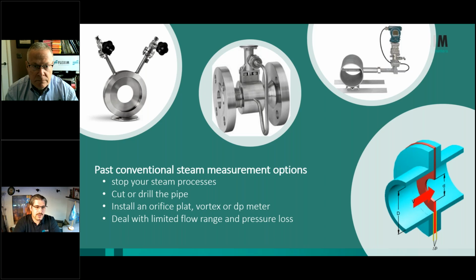all inline. So as soon as you want to have a steam measurement installed into your system, the first thing you need to do is stop your steam process, cut the pipe, open it, drill it, whatsoever. Then you have to install, for example, an orifice plate, what you see on the top left, a vortex meter in the middle, or any kind of differential pressure probe on the right-hand side. So that is something you need to physically install into your pipe, then close everything, weld it up again, make sure it's not leaking, get your safety documentation done, and so on. And then you still have to deal with a limited flow range and pressure loss, because all those metering principles have quite something in common, and that is quite a limited flow range. And this is something you need to consider if you're thinking about monitoring your steam flow.